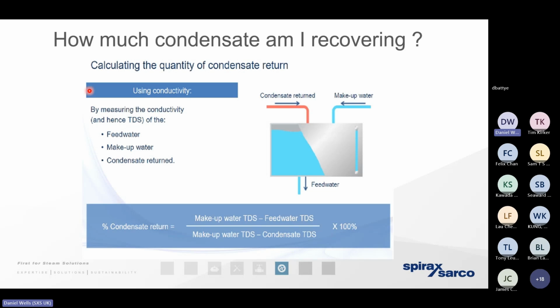The question we're often asked is, how much condensate am I actually returning or recovering? Quite often, if we ask that question of our client, in almost every case, they will say, we're recovering all of it. We're recovering all of our condensate. They often vitally, significantly overestimate the mass of condensate that is recovered and returned. Now, we can't meter that condensate because we know that if we've got a fluctuation in pressures, the result is we're going to get some steam that is evaporating, boiling off, and therefore we've got differing masses and volumes.